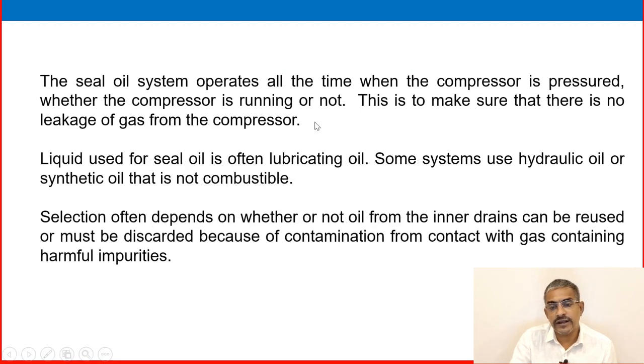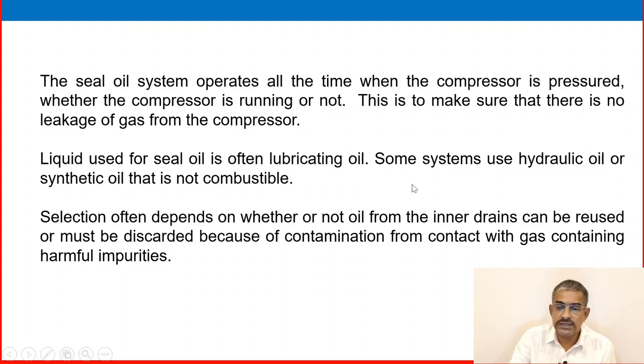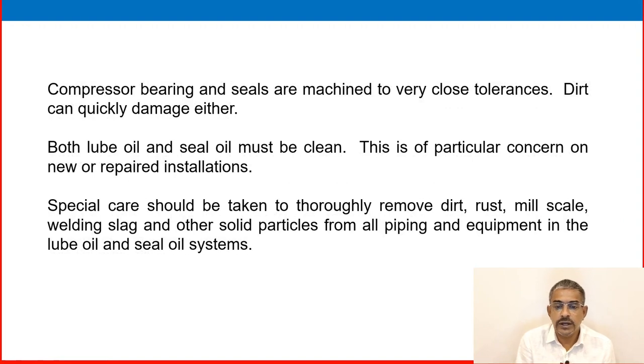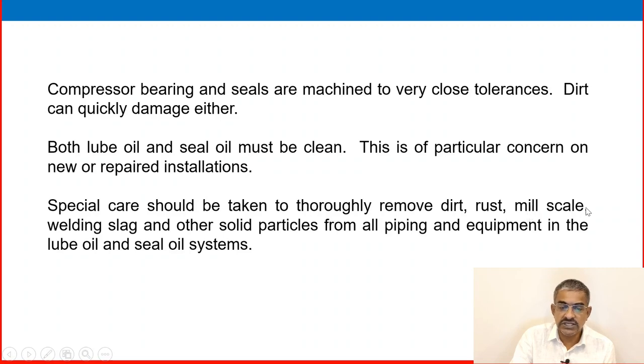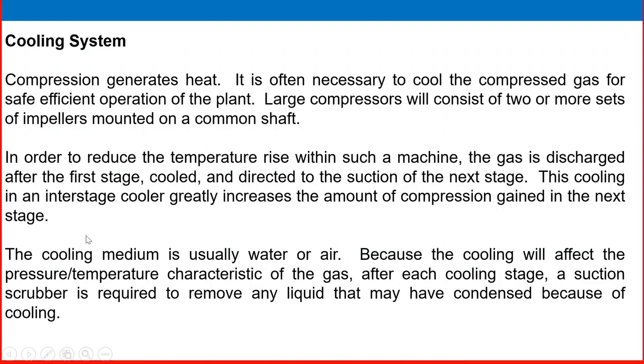The seal oil system operates all the time when the compressor is pressurized, whether the compressor is running or not, to ensure no gas leakage from the compressor. The seal oil liquid used is often lubricating oil, though some systems use hydraulic oil or synthetic non-combustible oil. Selection depends on whether oil from inner drains can be reused or must be discarded due to contamination from contact with gas containing harmful impurities. Compressor bearings and seals are machined to very close tolerances and can be quickly damaged, so both lube oil and seal oil must be kept clean — especially during installation and repair.